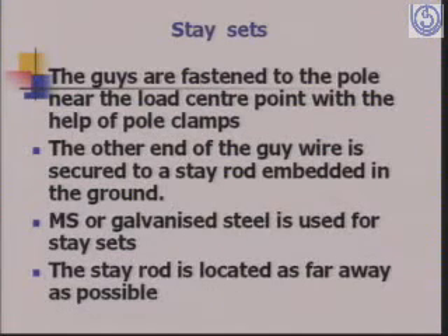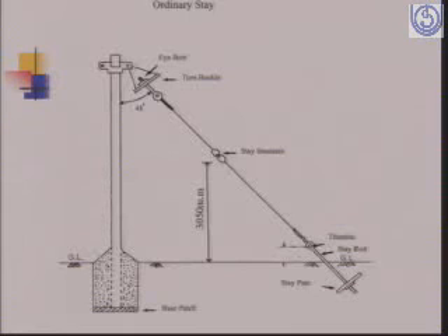The guys are fastened to the pole near the load center point with the help of pole clamps. The other end of the guy is secured to a stay rod embedded in the ground. MS or galvanized steel is used for stay sets. The stay rod is located as far away as possible. You can see this is the figure of how stay is provided. You can see the pole, how it is held in vertical position by the stay set. And you can also see the guy strain insulator or stay insulator at the middle of the stay. So this is how the stay set is installed.